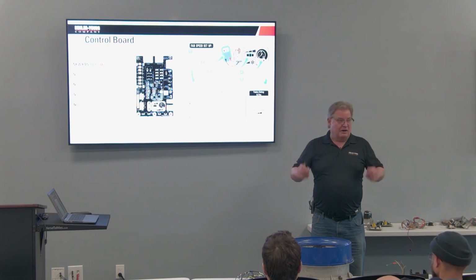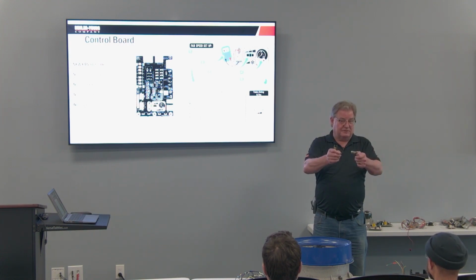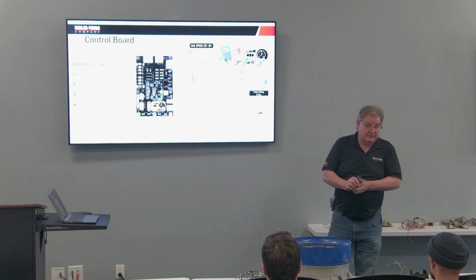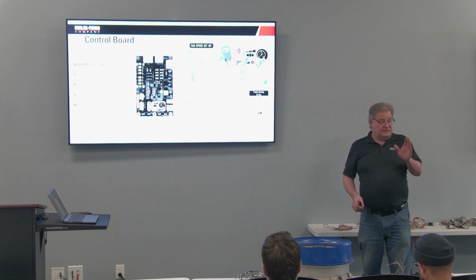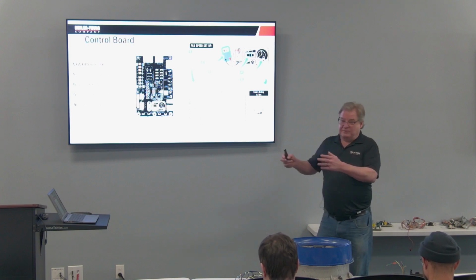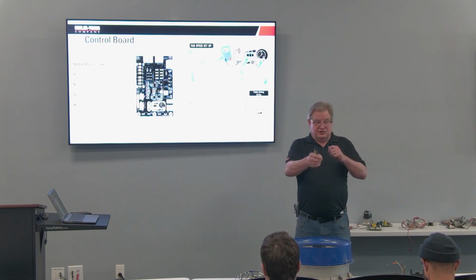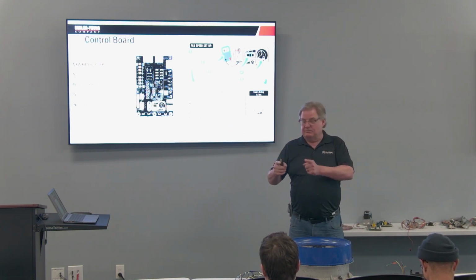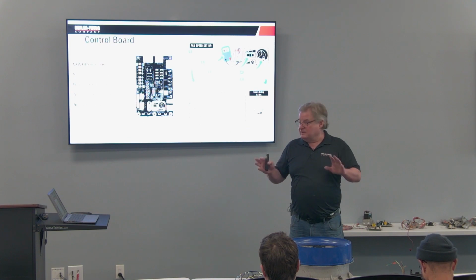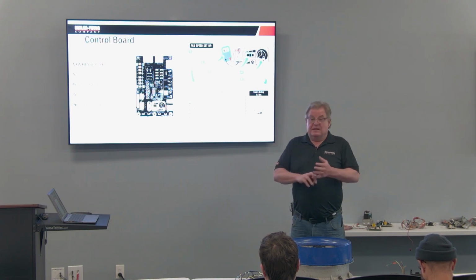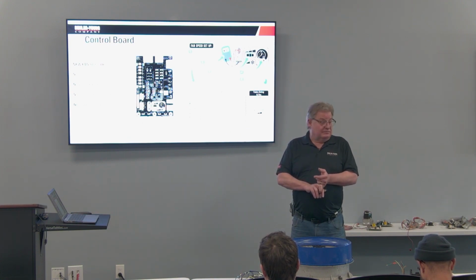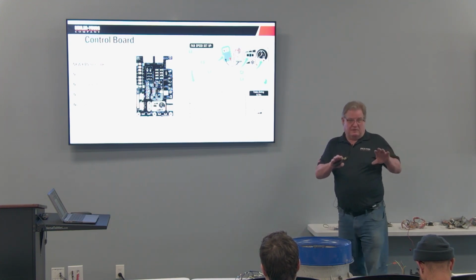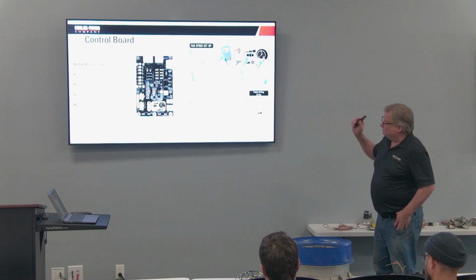First thing, power up. Check the primary voltage going to the transformer. If it's 208, you want to change the wiring on the transformer for 208. If it's in the middle, let's say it's 212, which way do I go, 230 or 208? Try it both ways until you get the highest output on your transformer. Is everybody following that? Because what will happen, it'll work, but in 6 months your service guy's back because the contactor coil's fried. That's one of those things that might not show up right away, so make sure you do that.